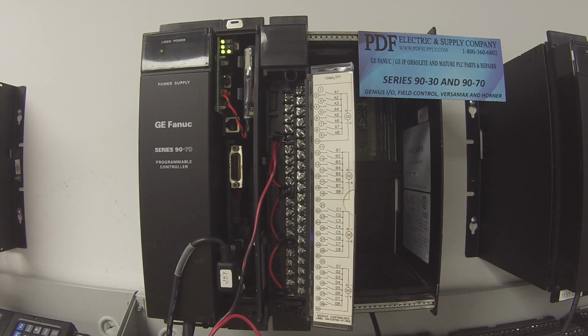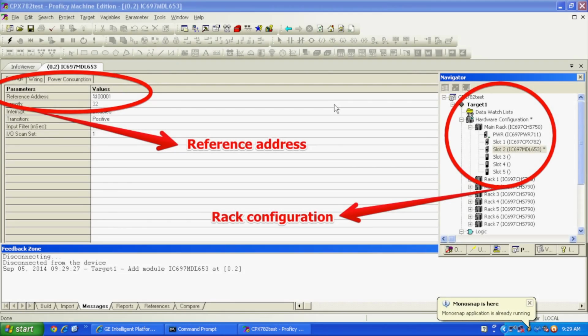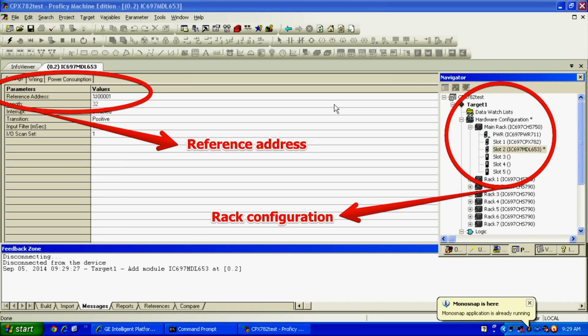On the Proficy Machine Edition side, what I've done is opened up my main rack on a new, clean file, and I've selected an IC697 CHS750 5-slot rack as I described. There's a PWR711 power supply, a CPX782 processor, and then I chose the IC697 MDL653, which is in slot number 2.